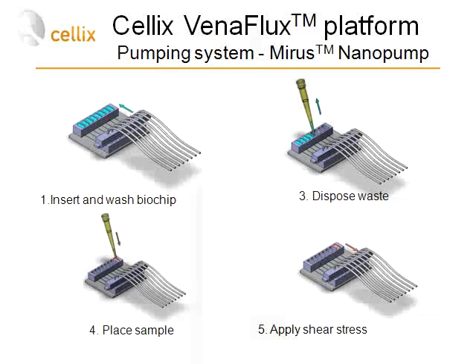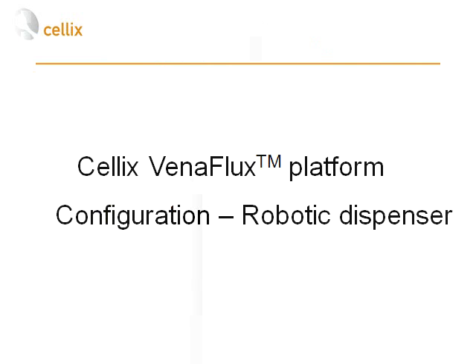This is how you conduct the experiment. You attach the cable from the multi-fluidic connector onto a biochip that has been pre-coated with different ligands or cells seeded onto it, then you wash the chip, dispose of the waste, and place the sample in the well. You apply shear stress at the predetermined value and observe the interaction of the cells with ligands or the endothelial cells lining the capillary. The chip is placed on the motorized stage and images from different positions of the chip can be saved and stored on your computer.